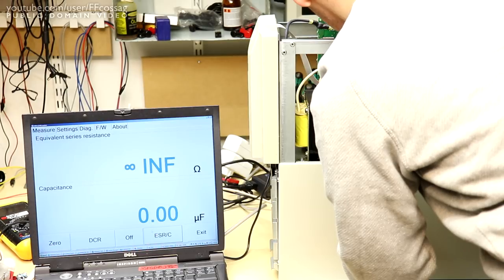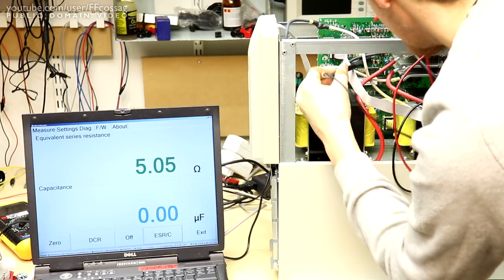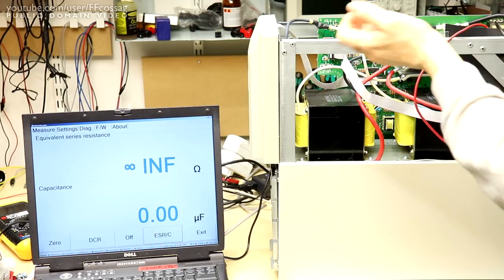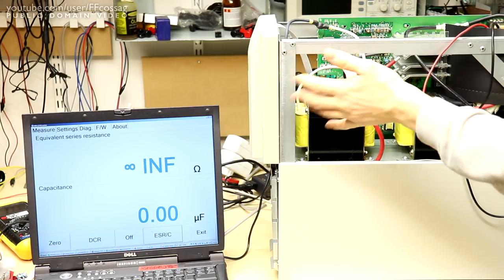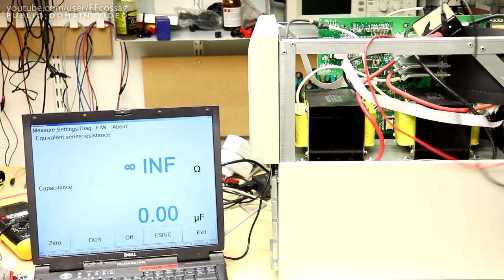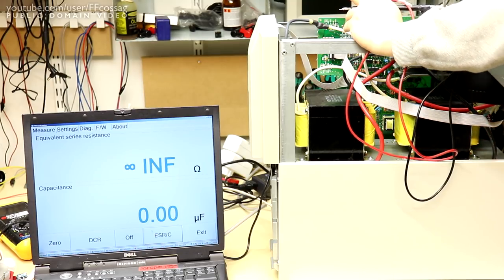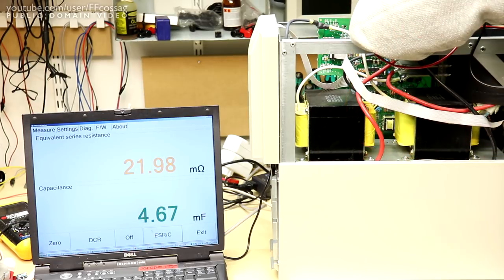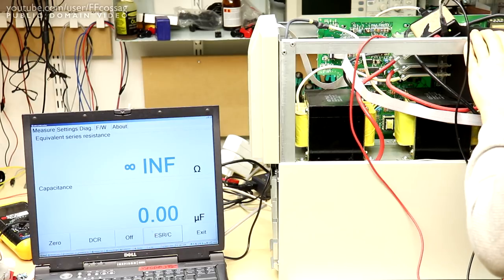So yeah, we're going to have to do all the 22s as you always need to in an APC UPS. Let's do another one just for the fun of seeing how bad they are. Yeah, 10 microfarad, 5 ohms. And it gets out, always the 22s. All the other caps tend to be just decent enough. And of course we can replace all the tiny caps just for the sake of it, but yeah, 22s in an APC UPS, they always go. And just for kicks, let's also probe the big giant caps, see how good they are. They tend to be usually in very very good shape. 20 milliohms, 4,600 microfarads. I actually have no idea what they're rated for, but they're going to be in good shape because they always are. Geez, it's almost as if I knew this was going to happen.